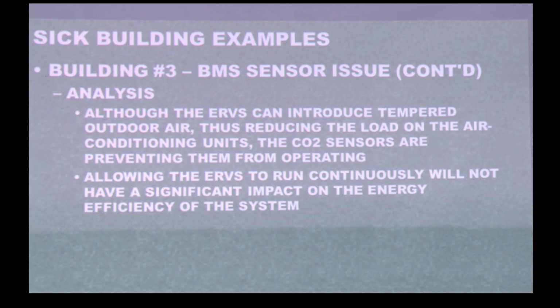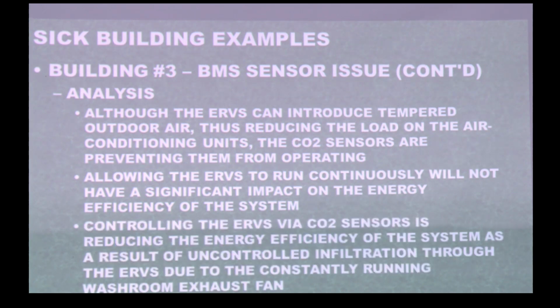Consider that if you are tempering your air using the ERVs, what's the penalty on the system for bringing that outdoor air in? It's pretty minimal. It's not a lot of air, but it's enough air to keep you comfortable. So why not just have the ERVs running continuously? Energy efficiency is going down because you're not leveraging the ability of the system to cool your outdoor air.